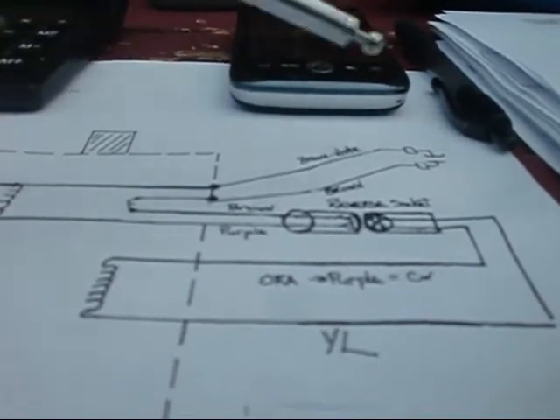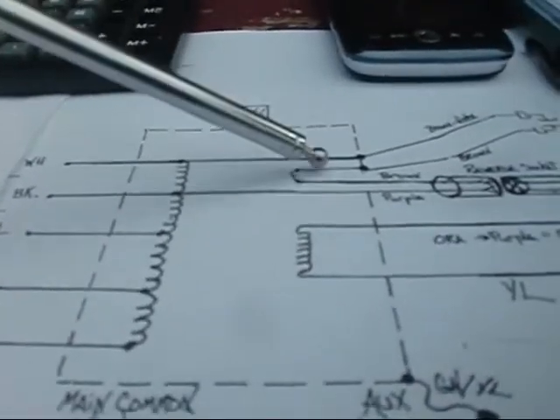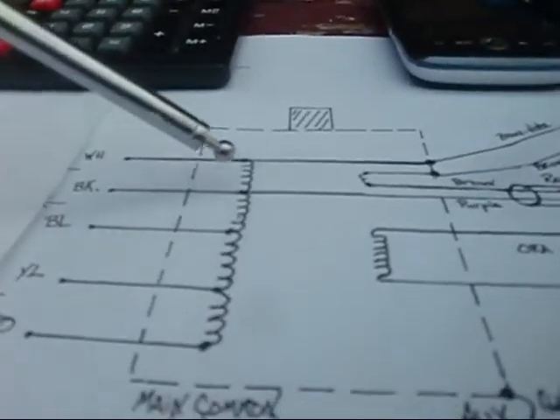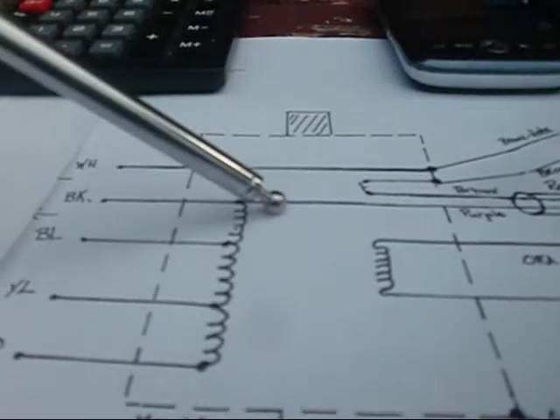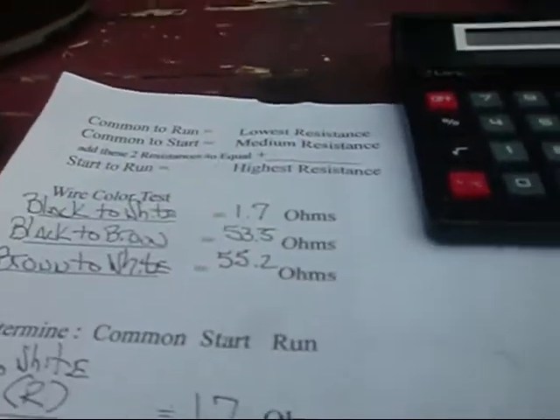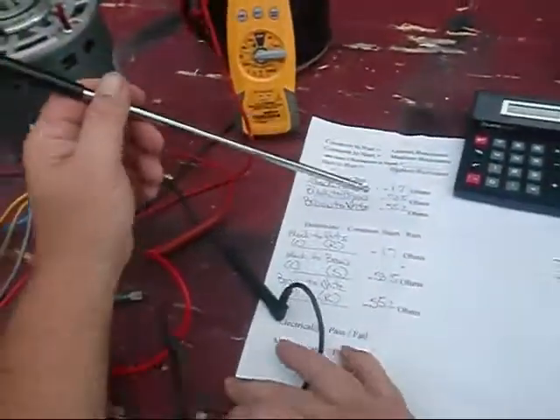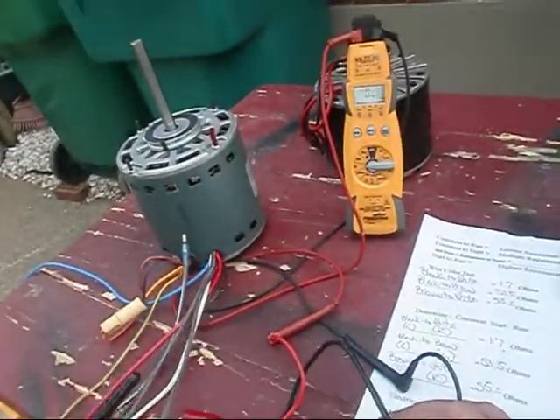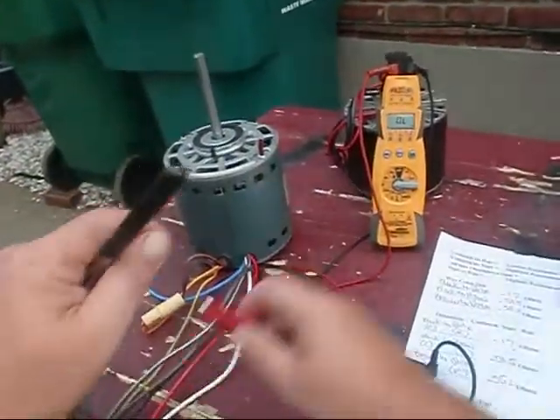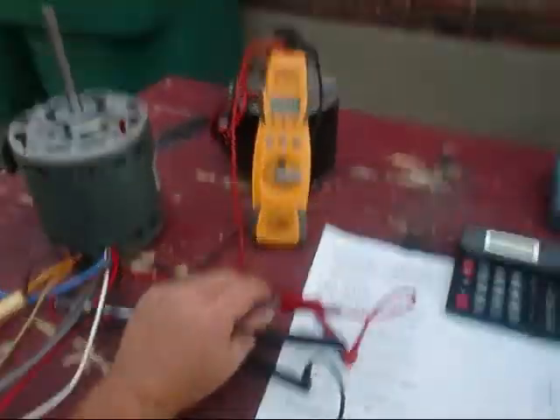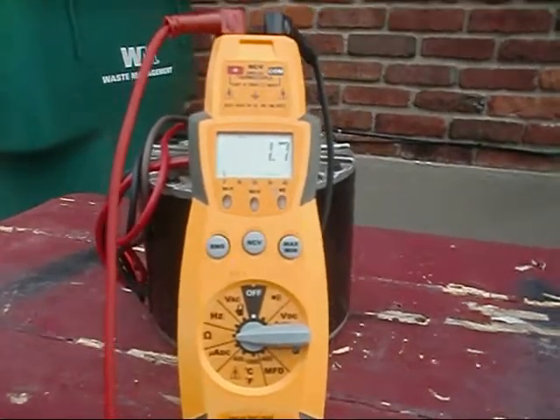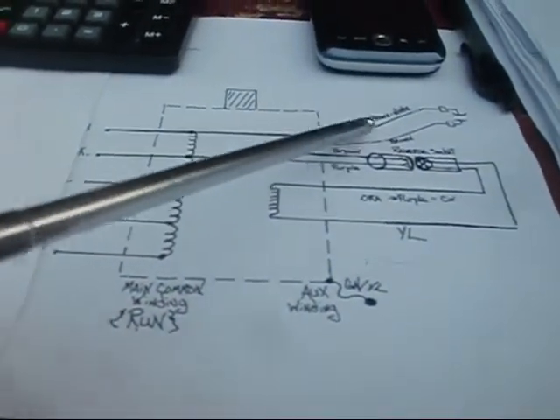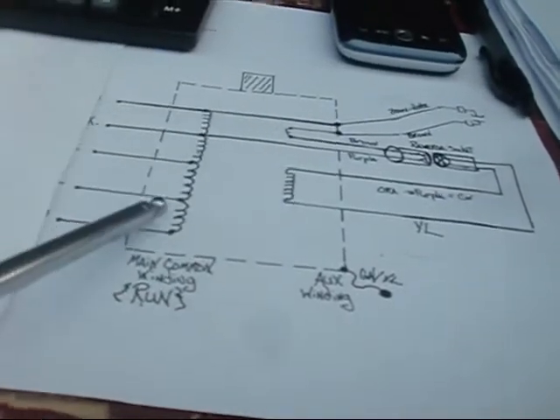What we did on this was we determined that this brown and white is actually part of the white, the run winding, the common run winding, and you can see it tied in right here. We proved a point that we knew that our black is actually common. So if you took this brown and white to this black, we should get that 1.7 that we've seen. Let's go ahead and do it one more time. The black is common. We discovered that by doing our tests. We're going to take it to the brown and white. Should be 1.7, 1.8, something like that. We got 1.7. 1.7 from the black to the brown and white right here. Our auxiliary winding, part of our auxiliary winding, which is actually tied into our main run winding.